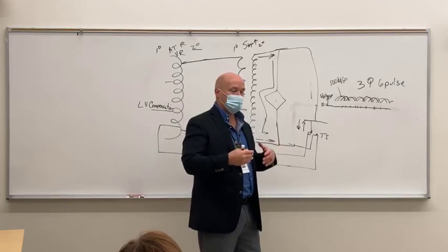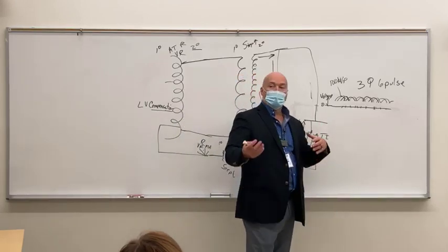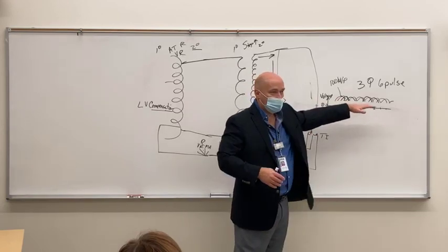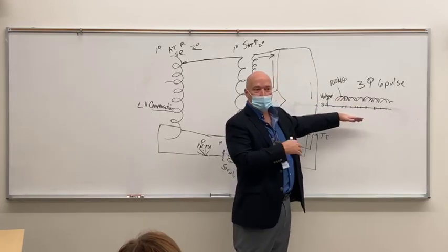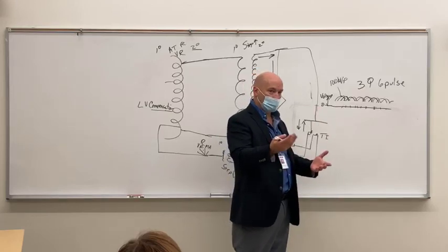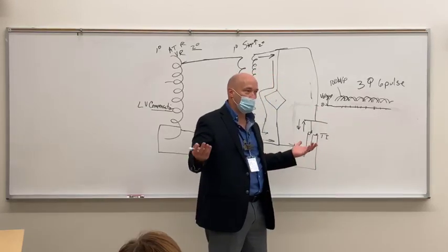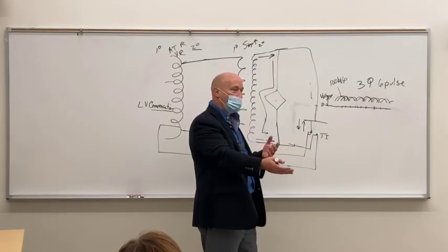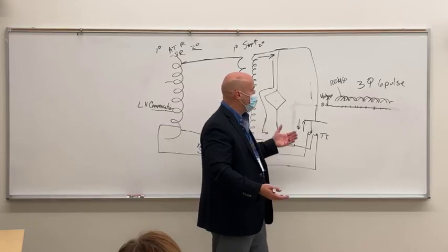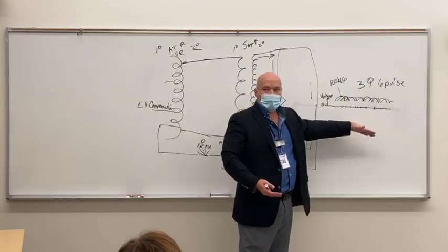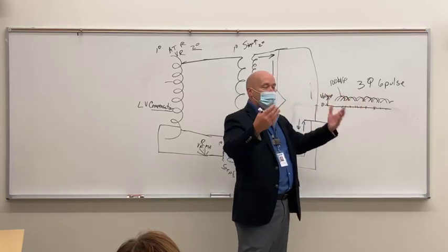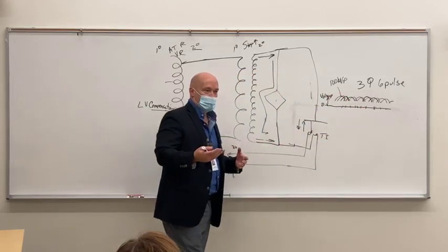Does that make sense? Because the average goes up, we never drop to 0, so these low energy photons are gone. They wouldn't do anything except absorb inside of the patient anyway, so they're useless for us. We need photons to penetrate through the patient. So it never drops to 0, the average beam energy increases, and therefore the quality of the X-ray beam increases.